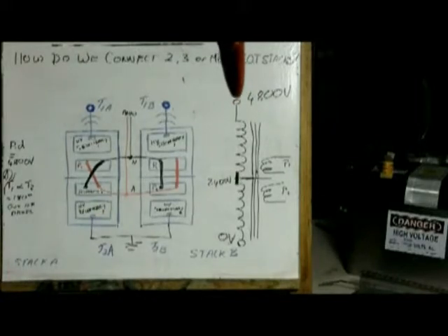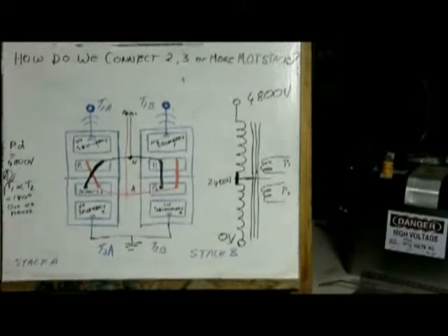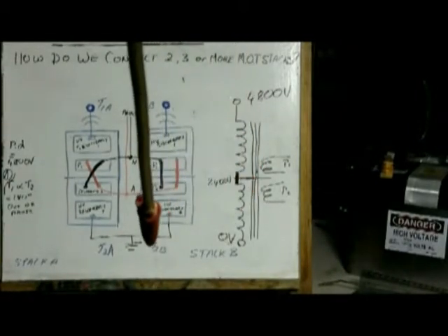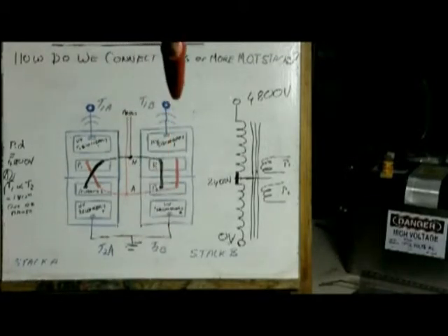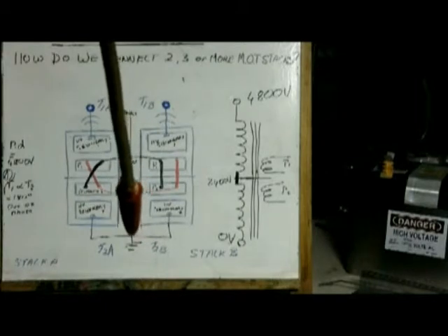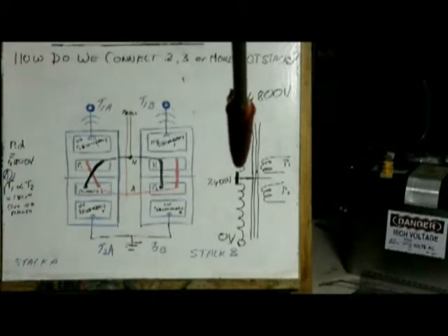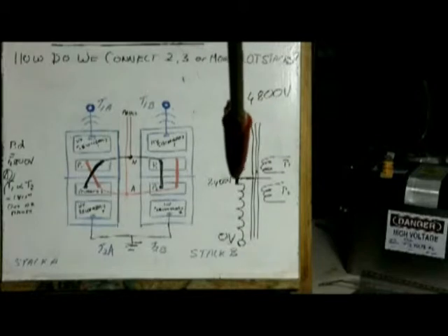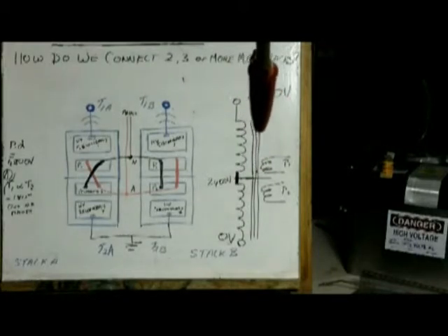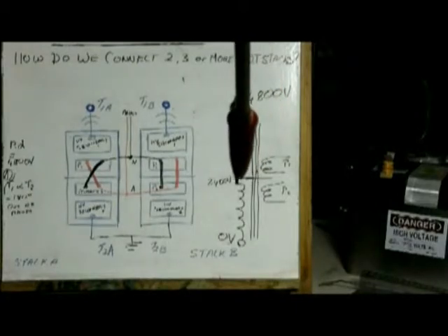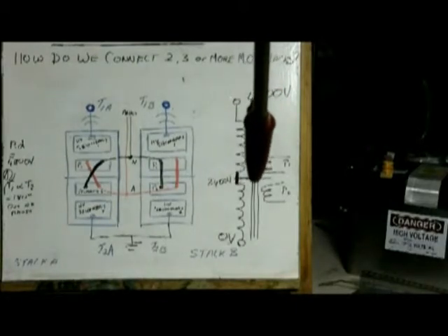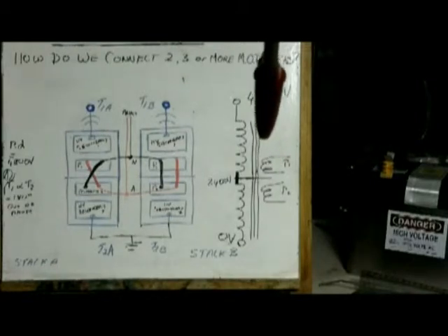Terminal T1 is now at 4,800 volts. So by connecting those 2 lower terminals together, and the only way to raise it to 4,800 is to ground those terminals, this automatically raises the core to 2,400 volts. You don't want 2,400 volts on the core. There's not much you can do about that because the secondary winding is actually connected to the core, as I've already described in the previous presentations.